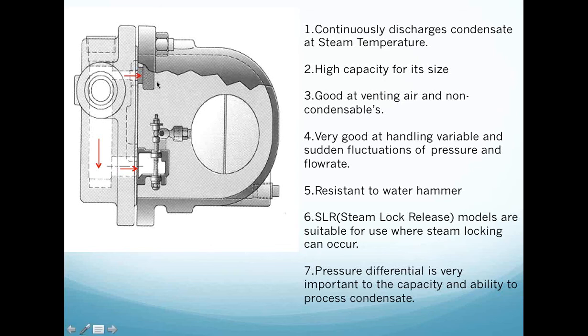I will tell you that that thermostatic element will be a weak link. If you took a piece of wire between both hands and started bending it, that wire over time would start to heat up and you would start to fatigue that wire. A thermostat that cycles, just like a bellows or a bimetallic thermostatic steam trap that cycles, expands, contracts, expands, contracts, over time those will start to fatigue and you will end up seeing degradation and potential failure. And that's what will fail inside of this floating thermostatic trap, will be that thermostat.